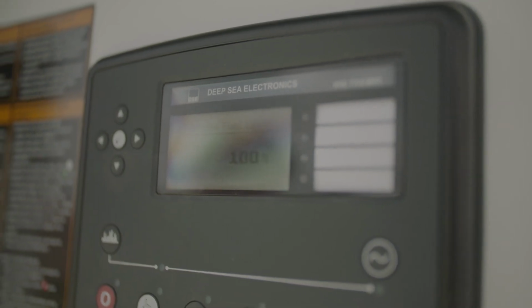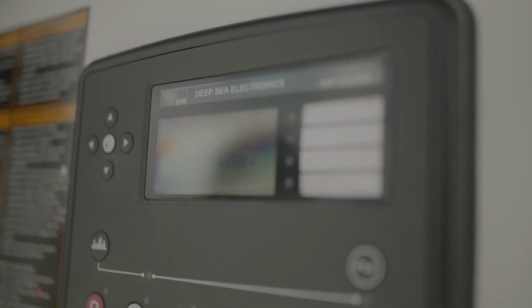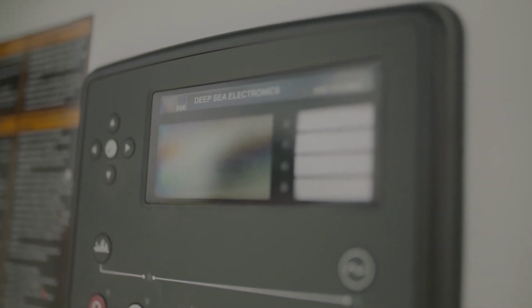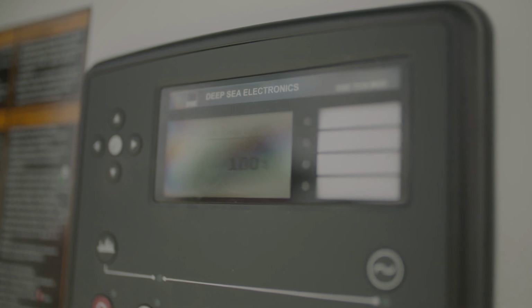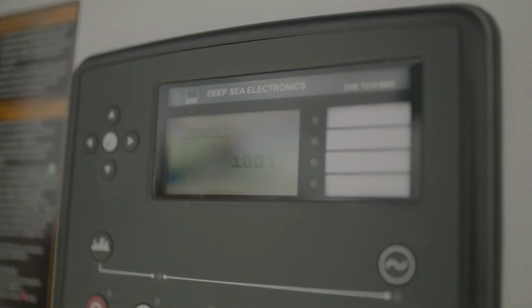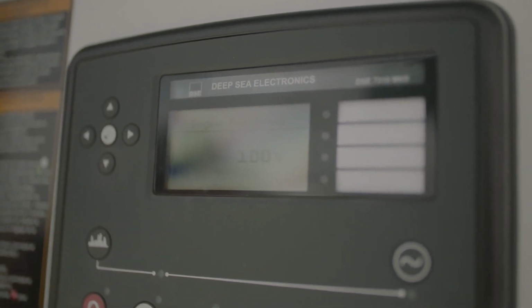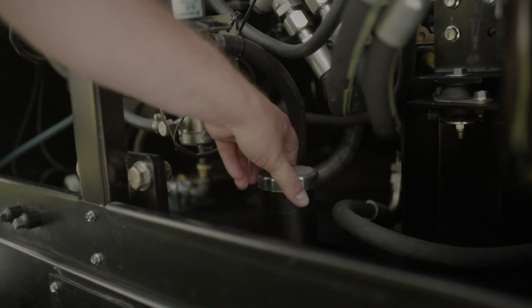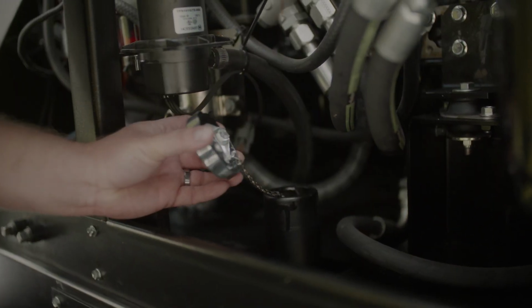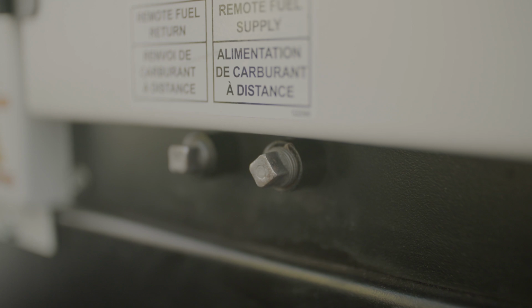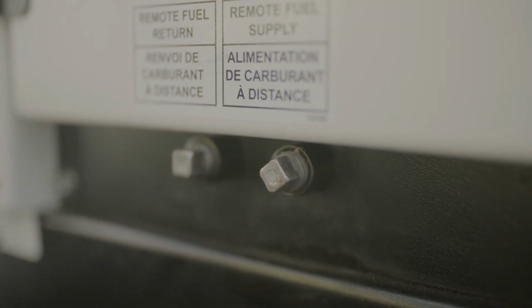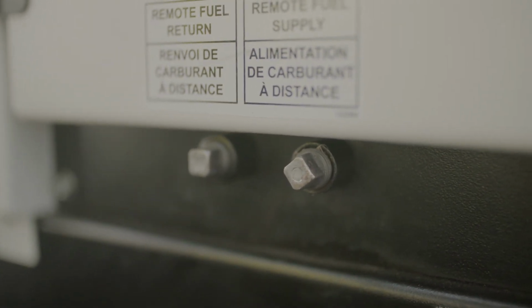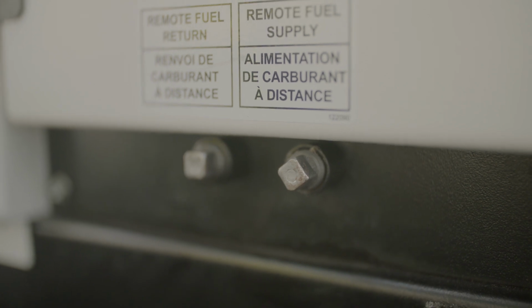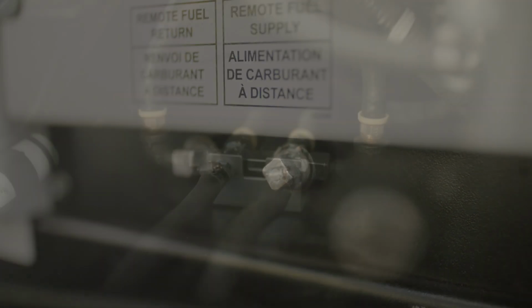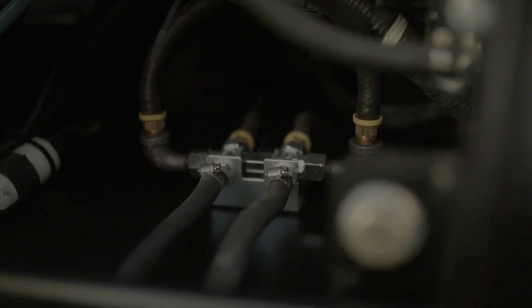Open the control panel door. Set the electronic controller to the on position. Allow the screen to turn on. Use the arrow buttons to scroll to the digital fuel level. Open the fuel cap to add fuel if necessary. Optional: the generator trailer is equipped with a remote fuel valve option to fuel the unit from a remote fuel tank. Refer to the operator's manual for remote fuel connection and operation.